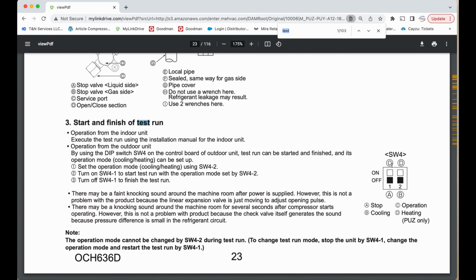But let's say you wanted to check it in heat. Well, at that point, you would physically have to walk over to the disconnect, turn power off, come back over to SW4-2, turn it on, then go back to the disconnect, turn the disconnect back on, and your unit would go into test run in heating mode. And then once you're done with doing your checks, then you go pull the disconnect again, and you would turn SW4 1 and 2 both off.